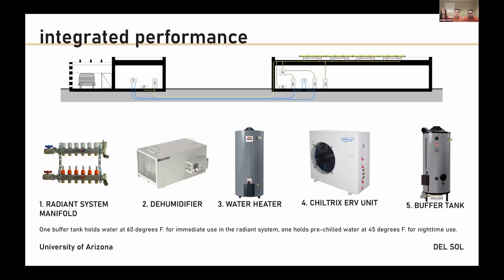During the day, all of this equipment can be powered by the solar array, but to reduce grid reliance at night, the system also pre-chills additional water. This is why there are two buffer tanks, one to hold water at 60 degrees and the other at 45 degrees. This second tank essentially stores renewable solar energy that can be utilized by the mechanical system at night. This strategy is significantly less expensive and less dangerous than chemical residential batteries, which can be a severe fire risk.